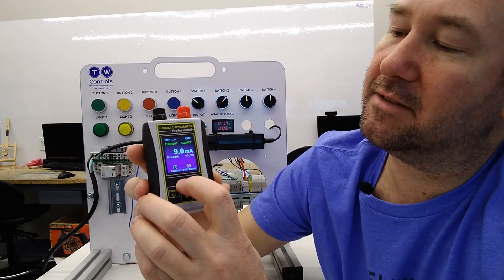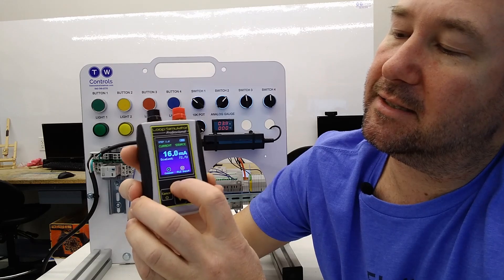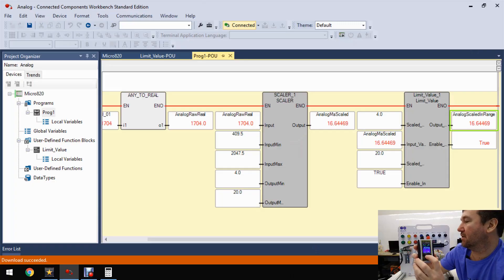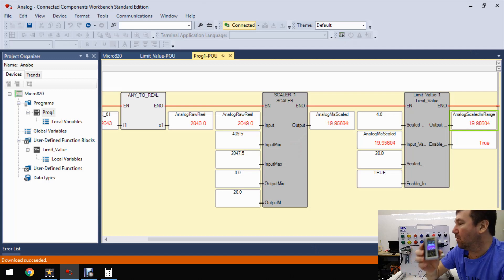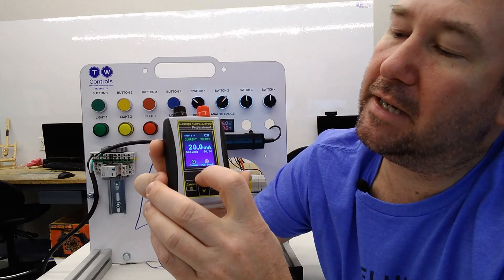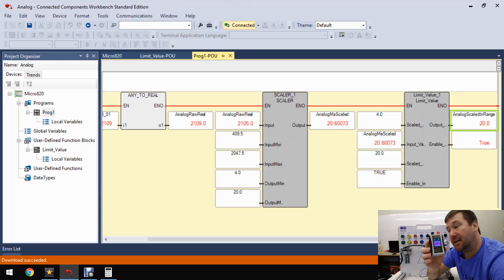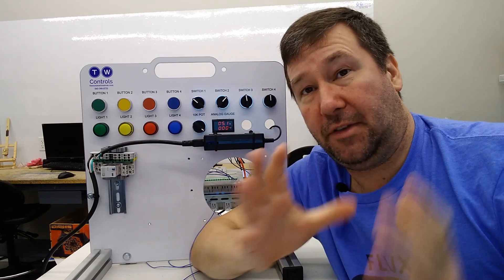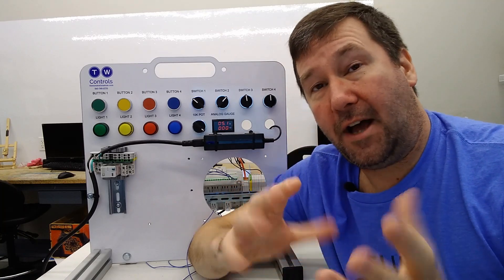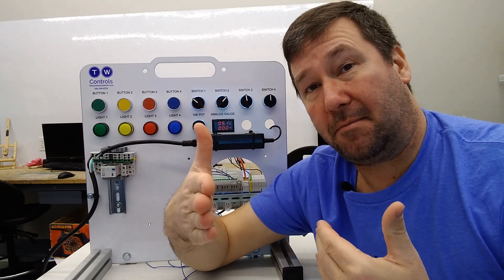So let's go up to the other side. Let's stop at 17. Make sure, yeah, we're showing about 17. And all right, at 20 we are showing 20. But if we get a 21, then we're showing only 20 here. So that'll hold our value within that four to 20 milliamp range.